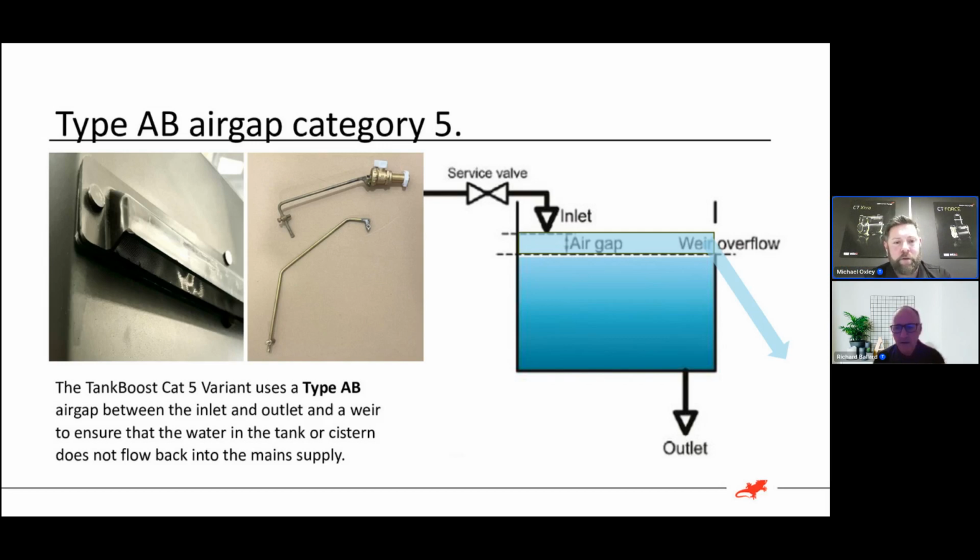Yeah, as I said earlier, Mike, it is one of the first products we've done where we have to consider, as a manufacturer, the air gaps and, for the domestic application, even volumes of water for you guys fitting them. We do various sizes, based on people's applications. There's no point in having a massive 450-litre tank of stored water if you're not going to be turning the water over regularly. So not only considering stagnant water, you're also considering what it's being used for.